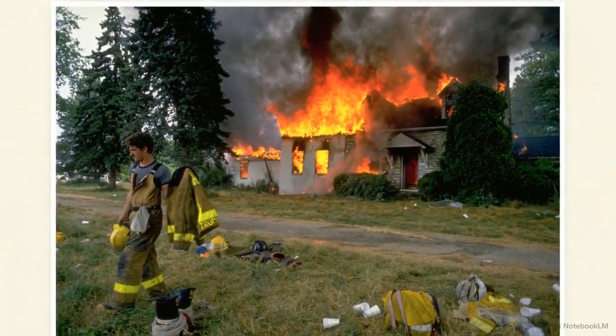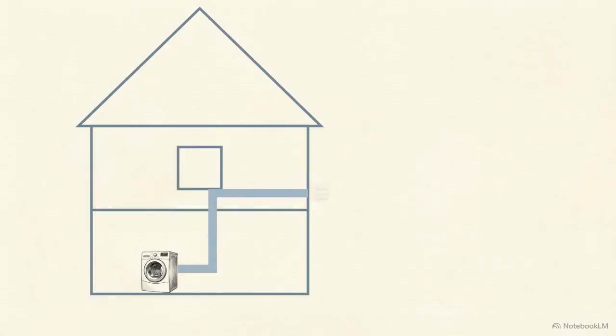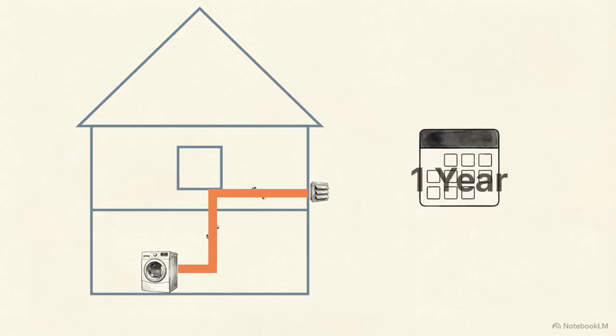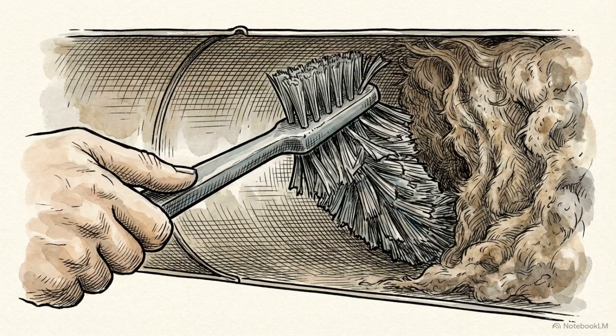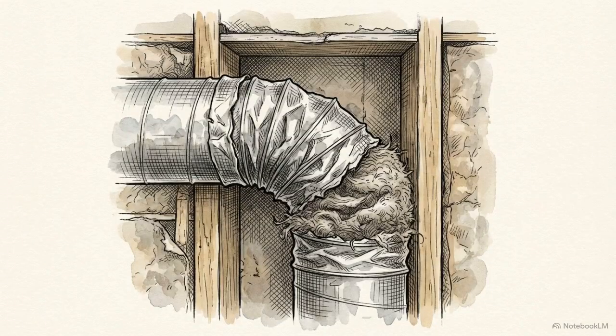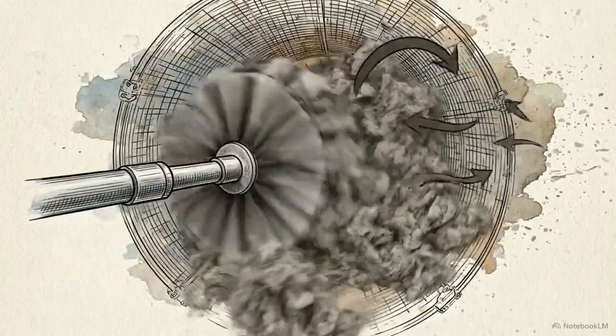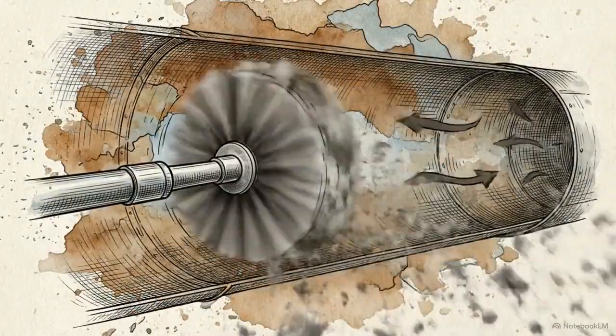To prevent this entirely, the National Fire Protection Association recommends a full cleaning of your dryer vent system at least once a year. Consumer-grade hardware store kits often fail to reach deep clogs, and a DIY approach cannot identify dangerous, non-compliant foil ducting hidden in your walls. Professionals tackle this with commercial-grade equipment, using specialized rotary brushes and high-powered vacuums to scrub the entire length of the ductwork.